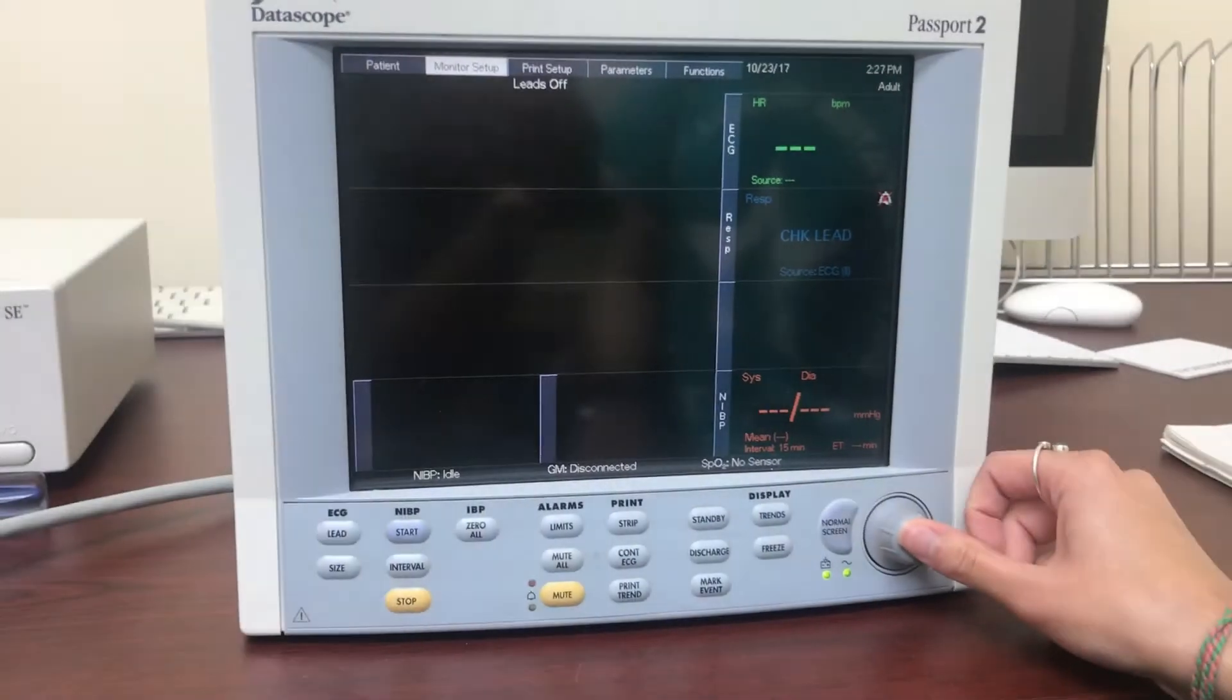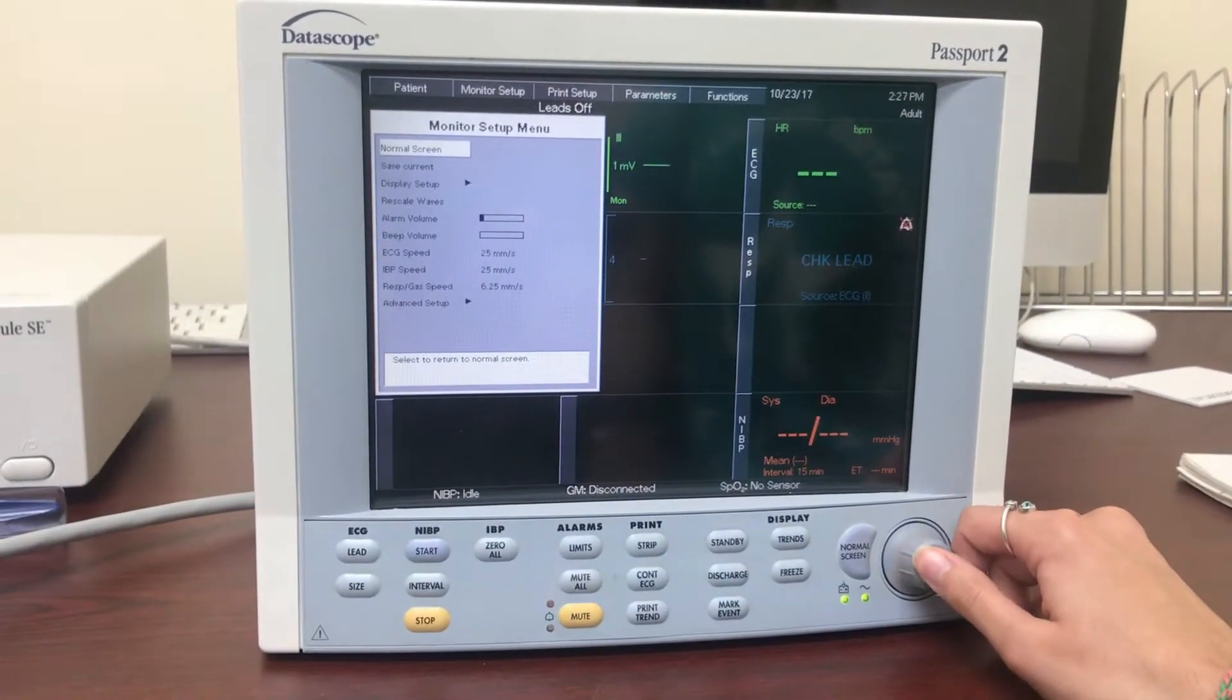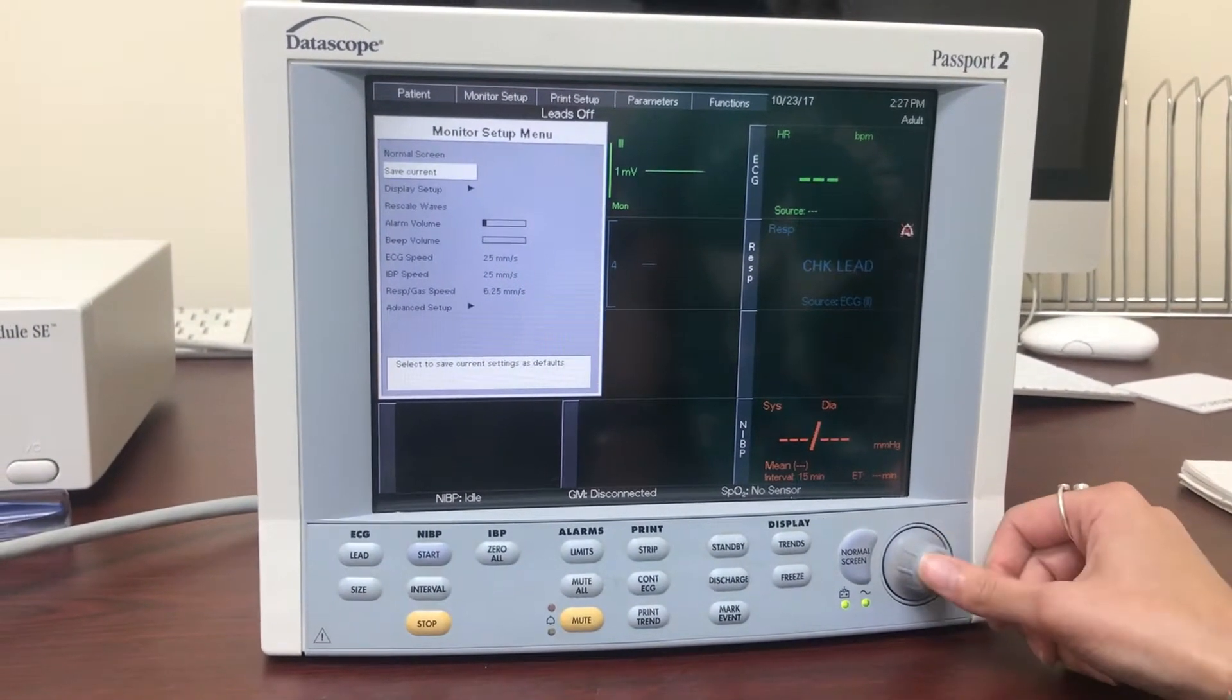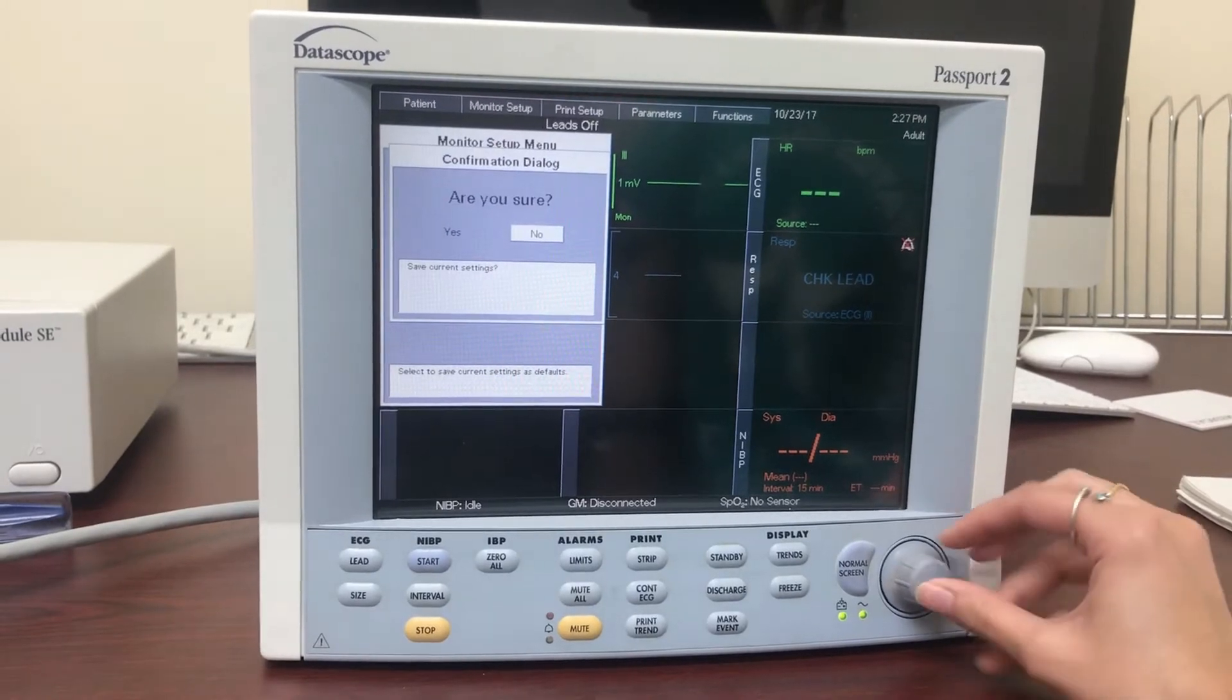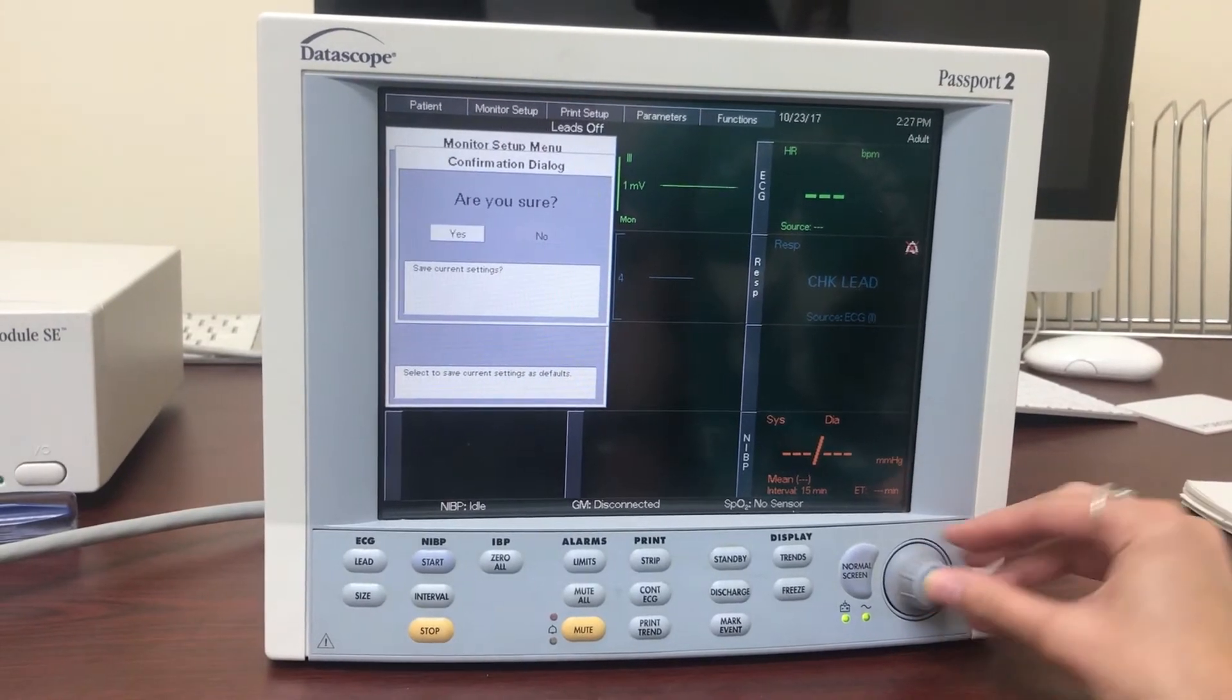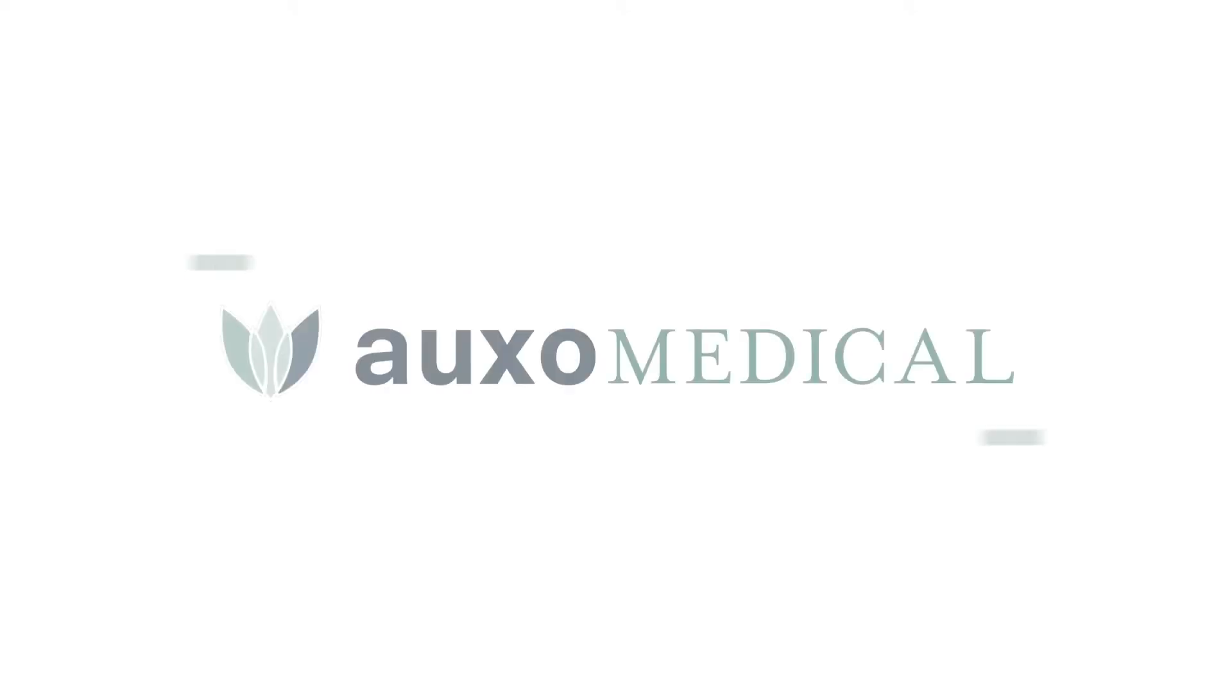In order to save the changes made to alarm limits, return to the main display screen, click on monitor setup, and press save current. Thanks for watching, have a great day!